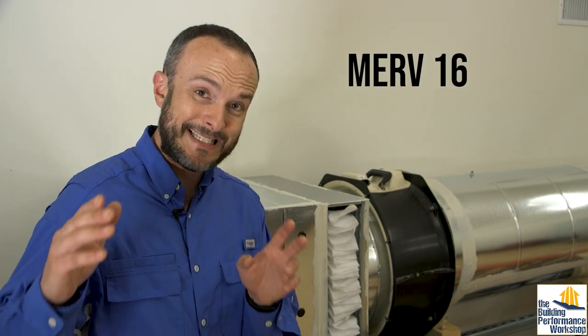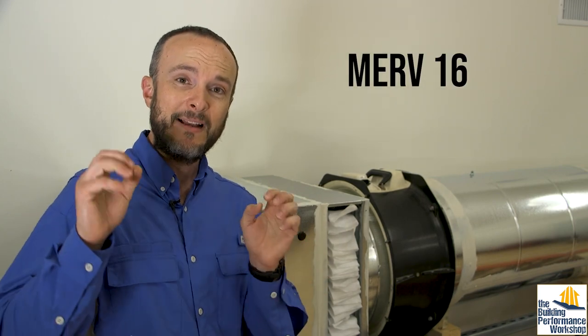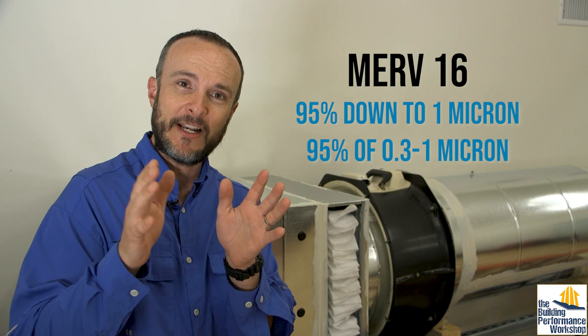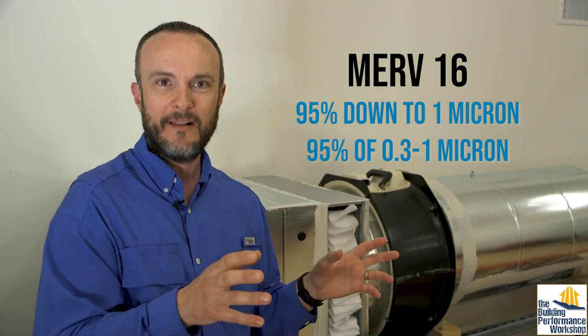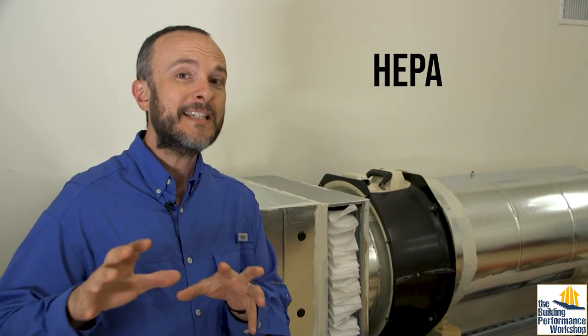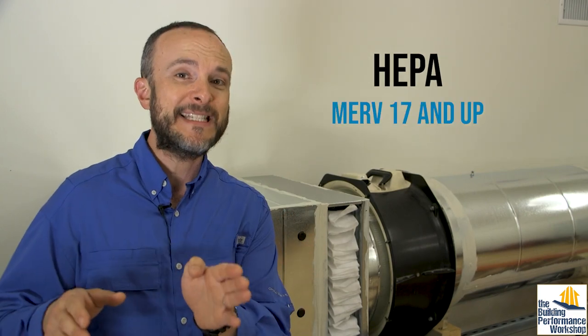Once you really get to a MERV 16, then you're grabbing 95% of all the particles that are big ones down to one micron and 95% of the smaller stuff as well. Now HEPA, which is hospital grade, that starts at MERV 17.